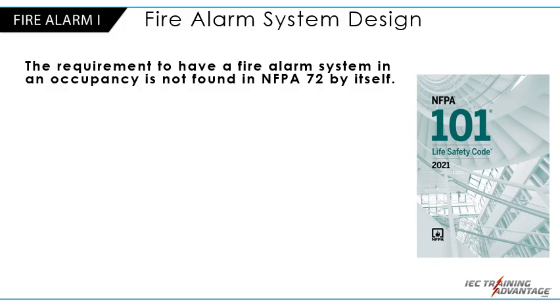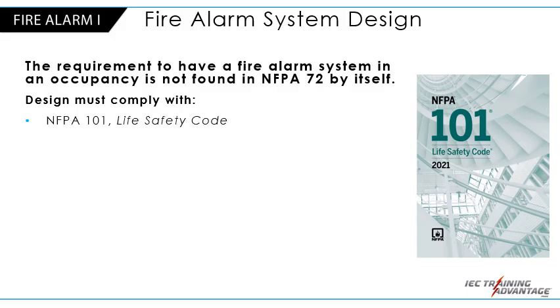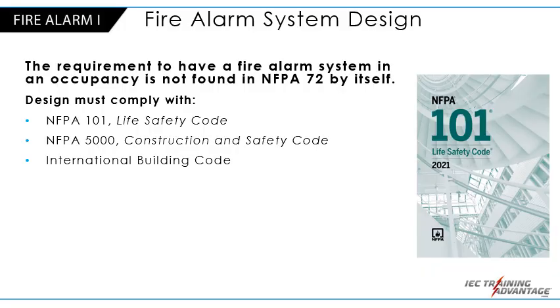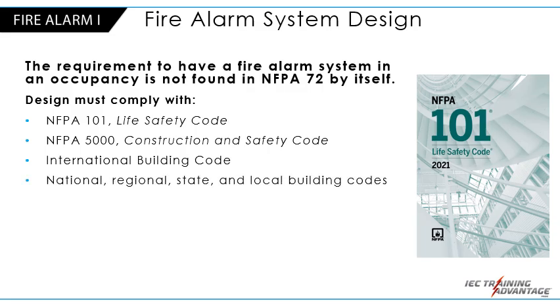The requirement to have a fire alarm system in an occupancy is not found in NFPA 72 by itself. There are other building codes and standards that require different types of systems dependent upon occupant and use. The design of these systems must comply with NFPA 101, Life Safety Code, NFPA 5000, Construction and Safety Code, International Building Code, national, regional, state, and local building codes.